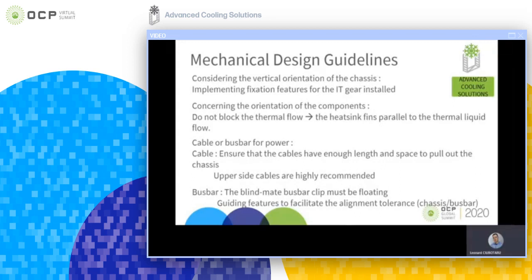Power transmission. The servers can be powered via cables or busbar. Both solutions work in immersion. If cables are used, one should make sure the cables have enough length and space to pull out the chassis. Preferably, upper side connections for cables should be used. If the power is transferred via busbar, then one must ensure the floatability of the blind mate connector and guiding features to facilitate the alignment.